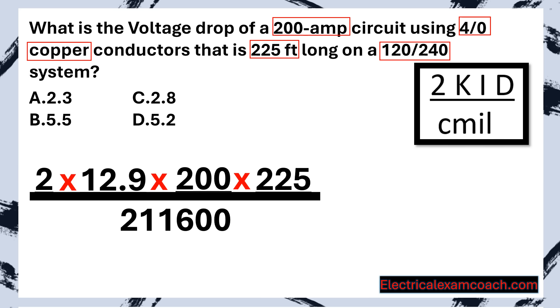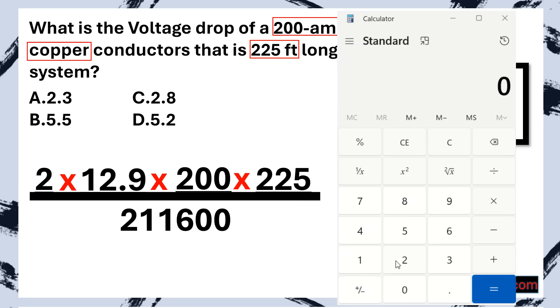Now, all we have to do is go to our calculator and plug it in. We take 2 multiplied by 12.9 equals, multiplied by 200 equals, multiplied by 225 equals. And then we divide that by 211,600. And it's as simple as that. That lets us know that we have a 5.48, which we would round up to 5.5 voltage drop on this circuit. And we select B. Great job.